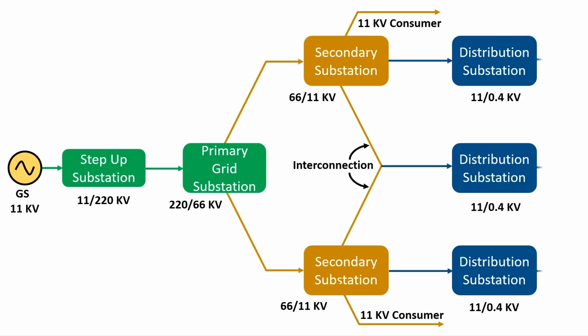The electric power from 11 kV lines is delivered to distribution substations. These substations are located near the consumers' localities and step down the voltage to 400 volt 3-phase 4-wire for supplying to the consumers. The voltage between any two phases is 400 volt and between any phase and neutral it is 230 volts.